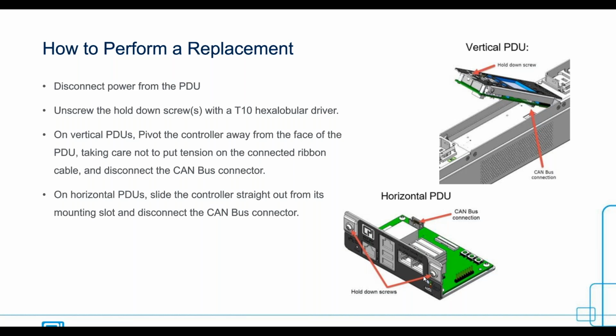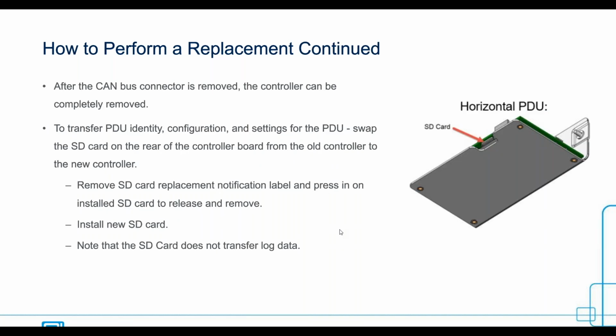The next important step is to properly swap the SD card into the new main controller module. To do this, remove the SD card by pressing on it. You'll hear a slight click sound to indicate it's loose, and you will visually see the SD card come out. Then you can install it in the new controller module and press until you hear a click sound and visually confirm it's been inserted. You can double check by shifting the controller a bit to notice that it doesn't fall off.